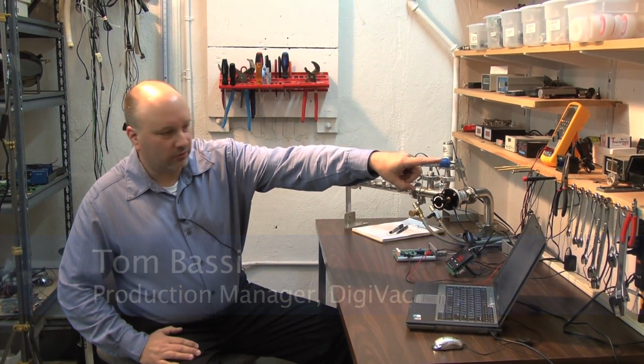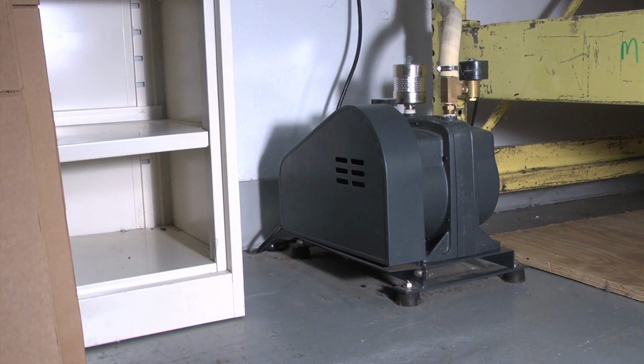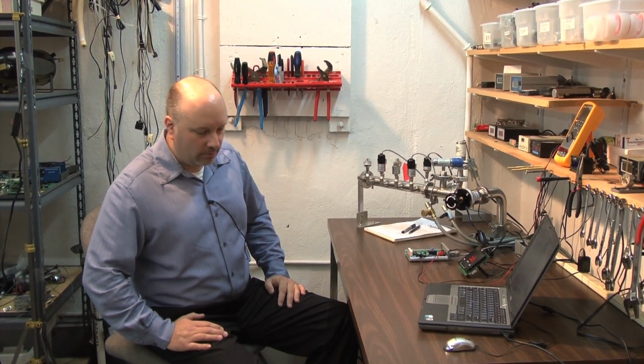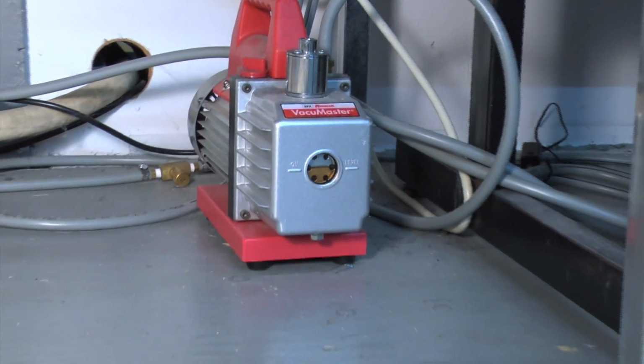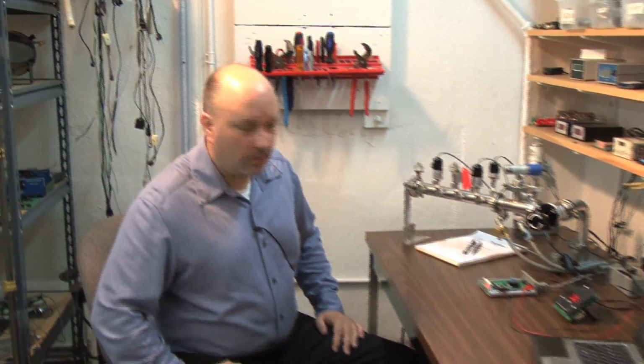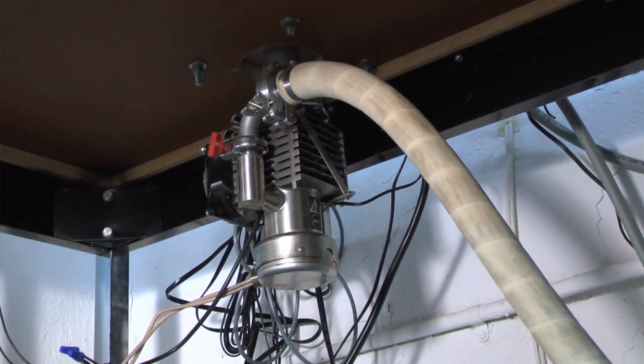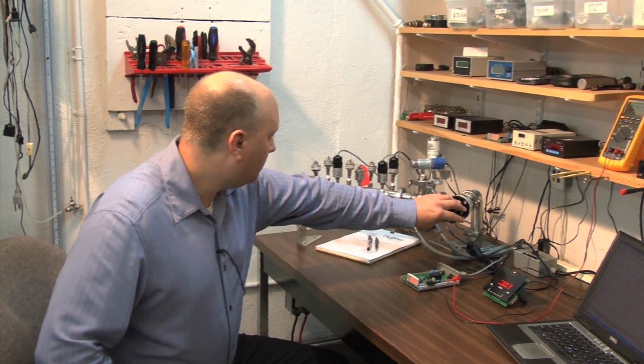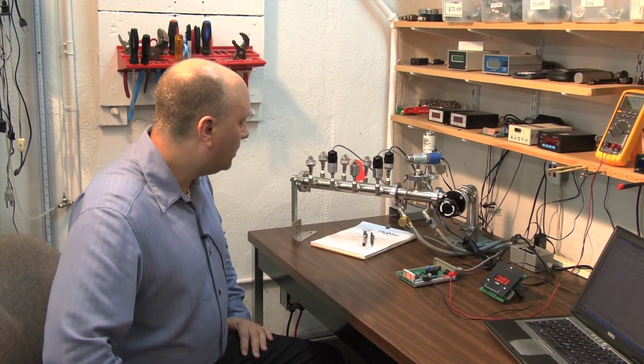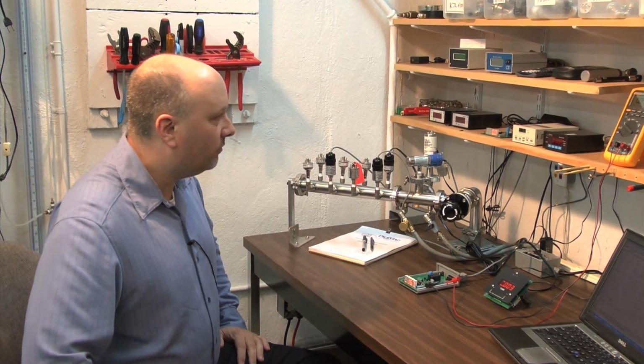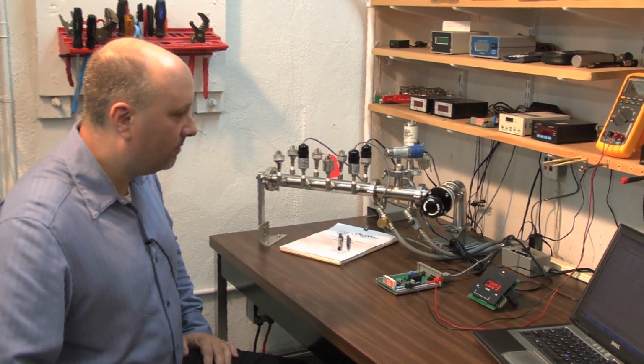In order to calibrate our instruments, it takes 3 vacuum pumps. The first vacuum pump, outside behind the wall, is a rotary-driven oil-based pump. Our second pump is a small, rough vacuum oil-based pump. Our third pump is a high vacuum diffusion pump mounted underneath the table. This vacuum manifold contains 10 ports for calibrating customers' gauges, and we have a wide array of test standards.